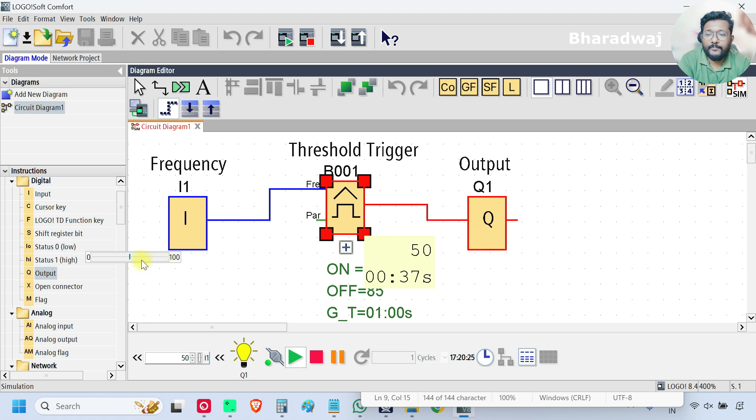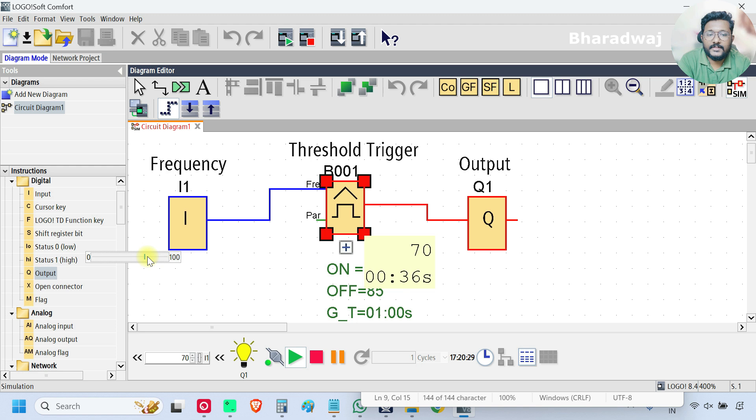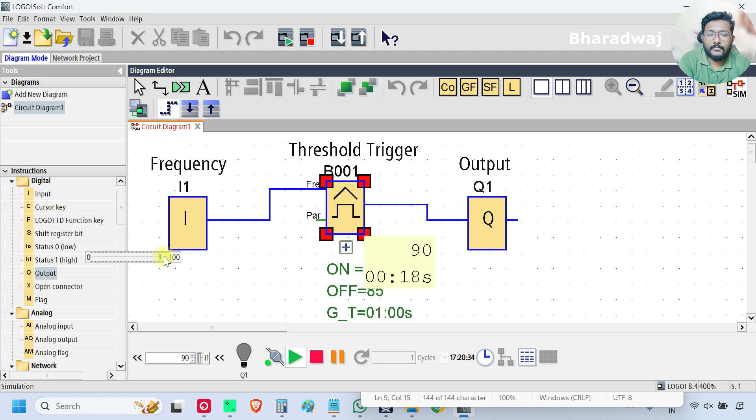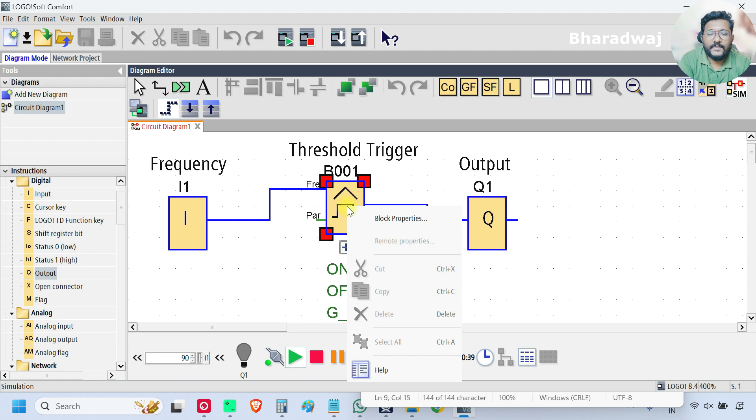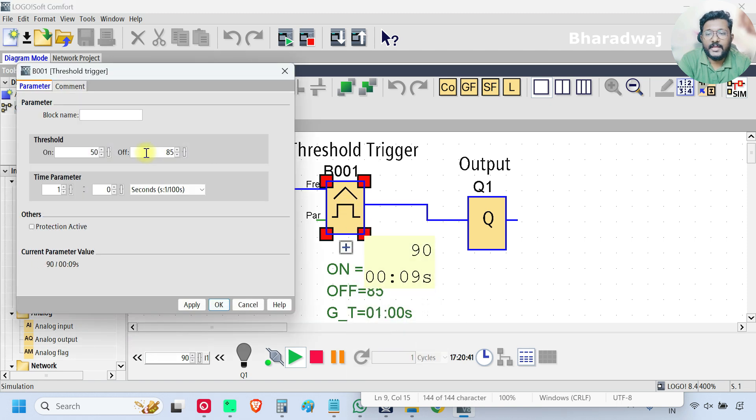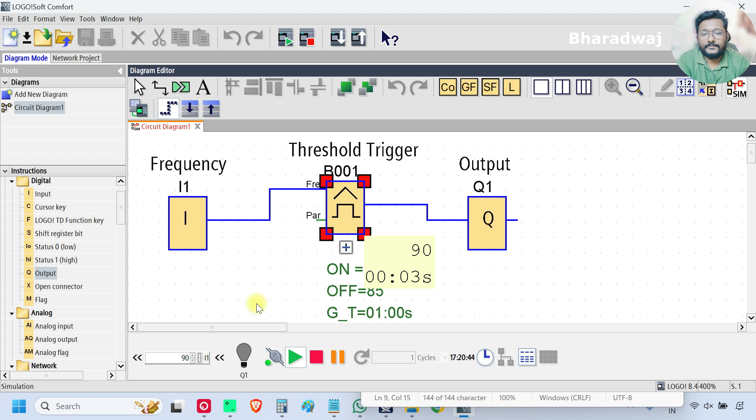And then still increasing the frequency input frequency 70, 80, 90. Output is off. Once the frequency reaches the off value, which is 85, then output will be off.